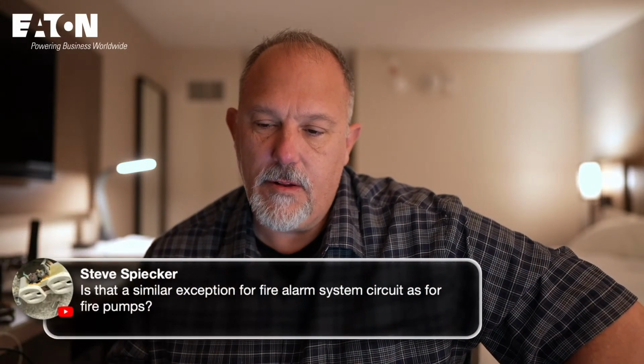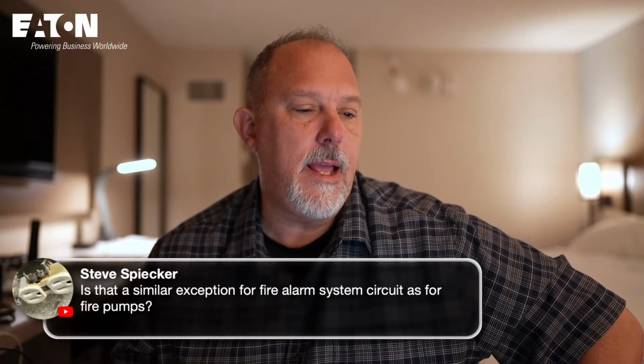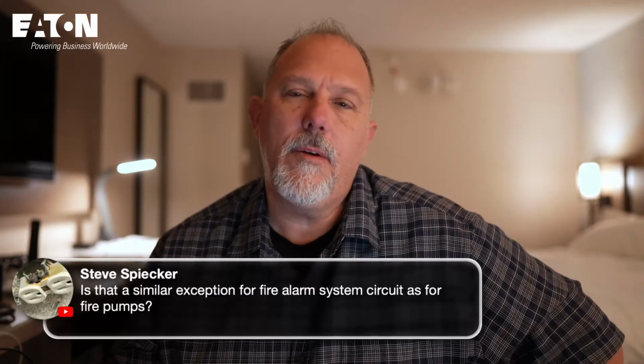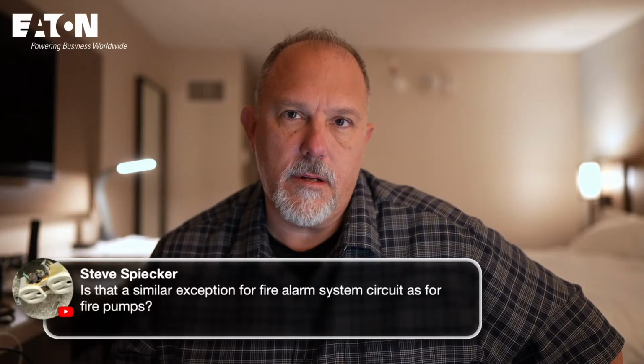Is that a similar exception for fire alarm system circuits as for fire pumps? Yeah, there is an exception on fire. I'll tell you what it says on fire alarm systems. Hold on. Fire alarm. Is that a chapter 7? Fire alarms. Where's it at? There it is, 760. Here's what it says in 760. Oh boy, a lot of changes in 760. Let's look for GFCI. Hazardous cables, power source. Where was the GFCI? What section was it, guys? Overcurrent protection. All right.